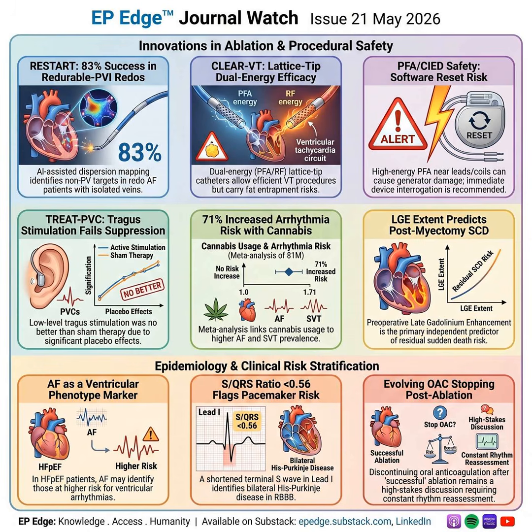In the Kovacs report, ventricular fibrillation was reproducibly induced during lattice-tip radiofrequency ablation near right ventricular ICD coils. Pectoral muscle contraction over the generator suggested that the ICD system may have become part of the RF return pathway, and the device standards editorial made the broader point: modern PFA waveforms and ablation current pathways may exceed what older device standards were designed to test. The practical implications are important.